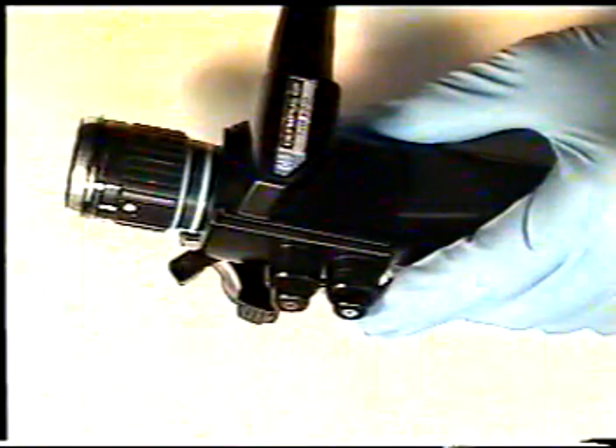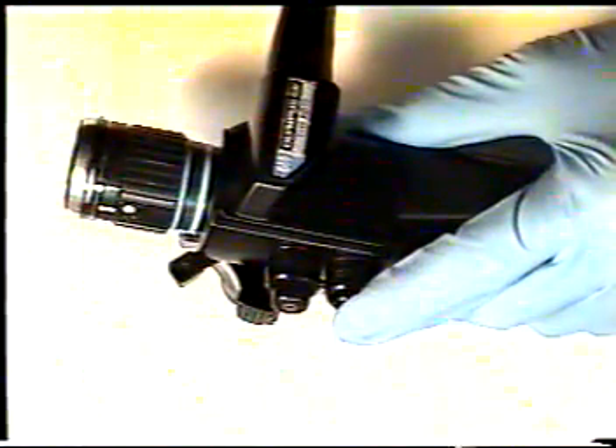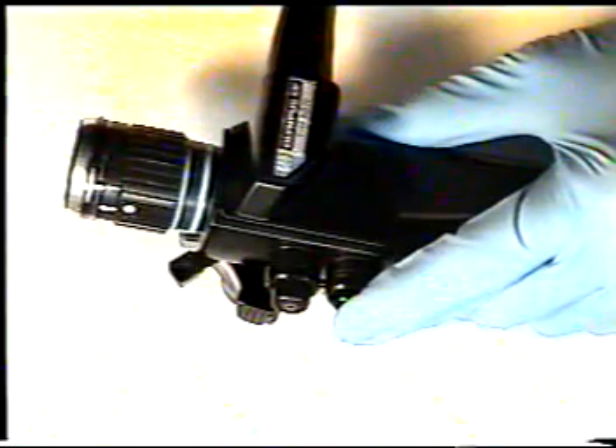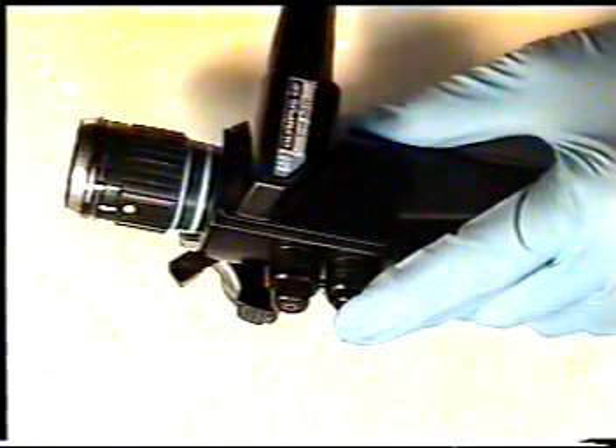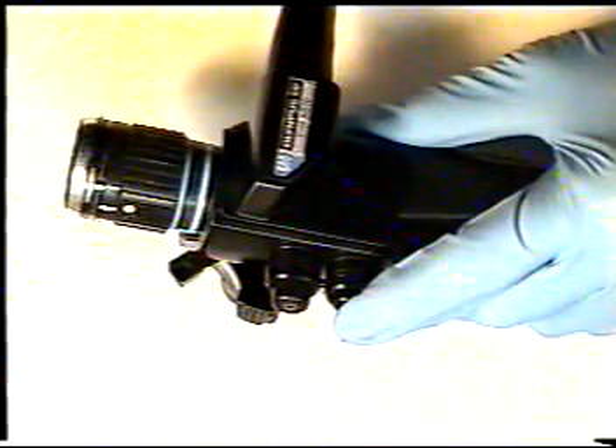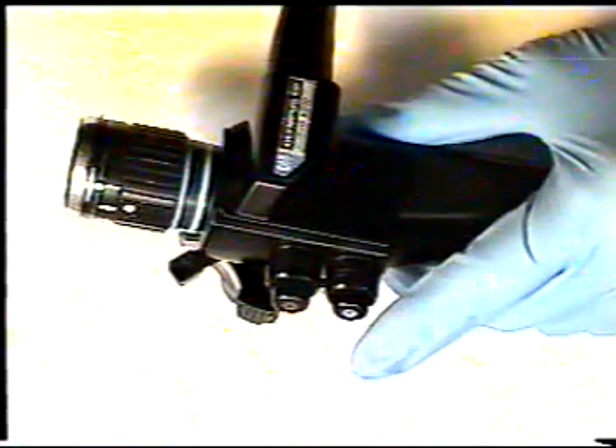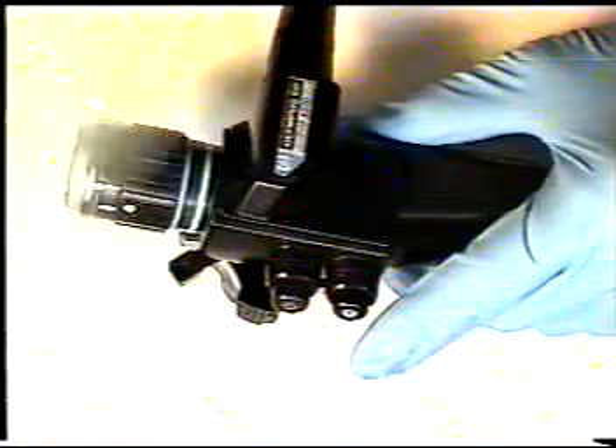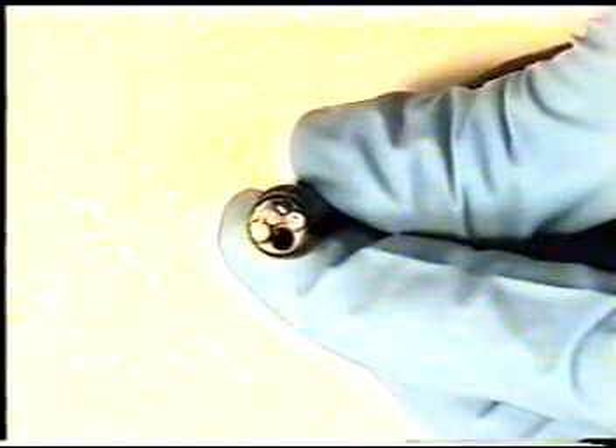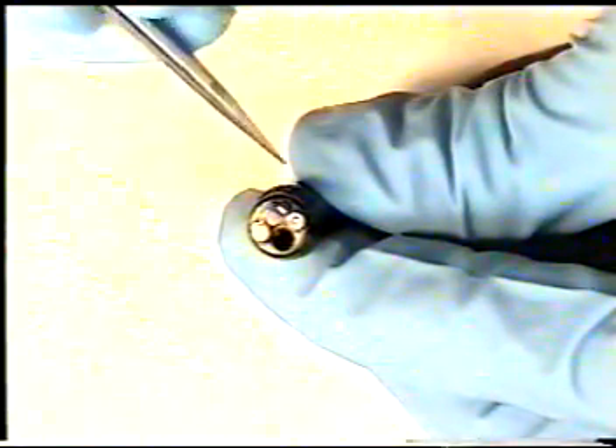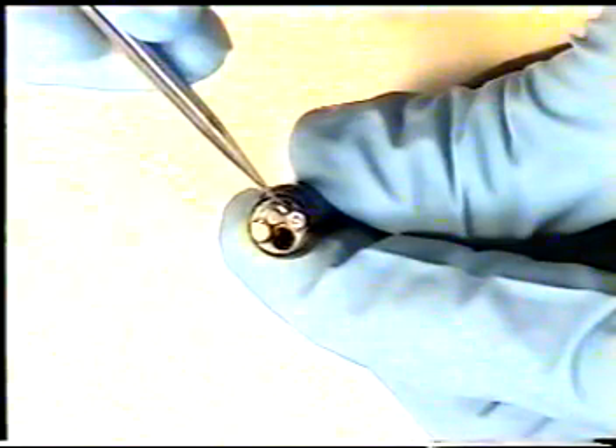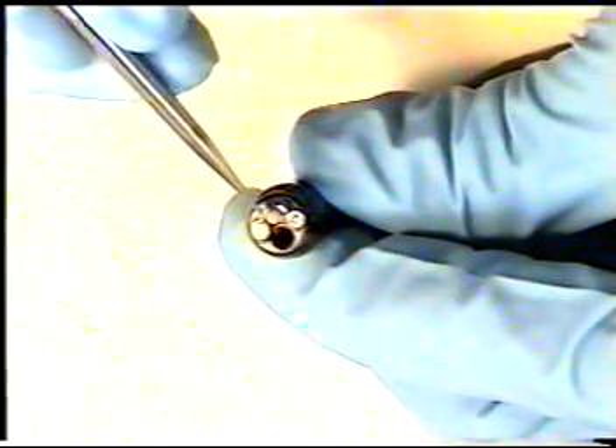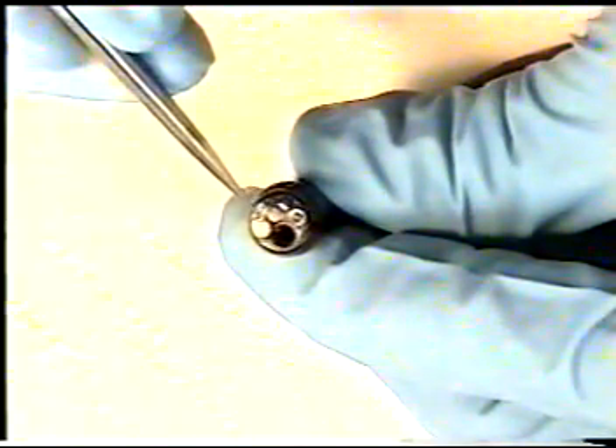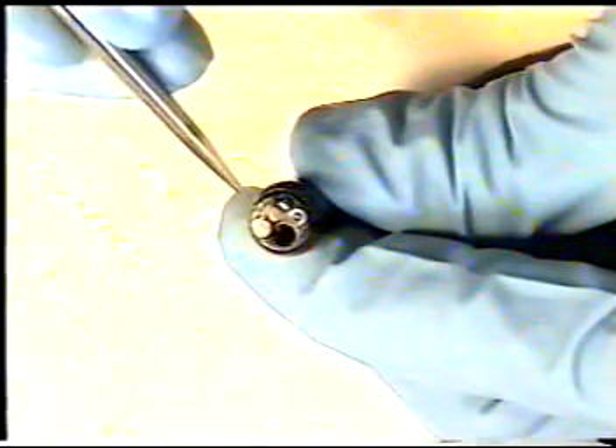When the air water button is depressed and little or no water is emitted from the air water nozzle at the distal end of the scope, it is time to replace the air water nozzle. First, locate the air water nozzle. It is the bent metal stainless steel tube which points towards the image guide lens or the video CCD lens.